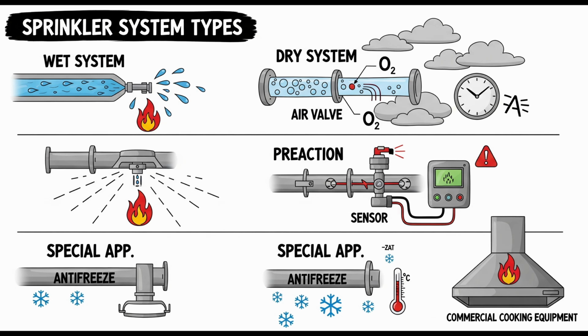A dry pipe system with a volume of not more than 500 gallons. That's about 1,900 liters. Right. That size is permitted without requiring a quick opening device. And it's not required to meet any specific water delivery time to the test connection. So for smaller volumes, the inherent delay is considered acceptable without extra measures. Seems reasonable. Yes, under 500 gallons. A slightly larger system, up to 750 gallons, around 2,800 liters, is also permitted without meeting a specific water delivery time, but only if it uses a quick opening device. So a QOD lets you have a slightly larger system volume-wise without needing to prove the 60-second delivery time. Correct. The QOD helps mitigate the increased delay caused by the larger pipe volume. It speeds things up. Okay, what else?